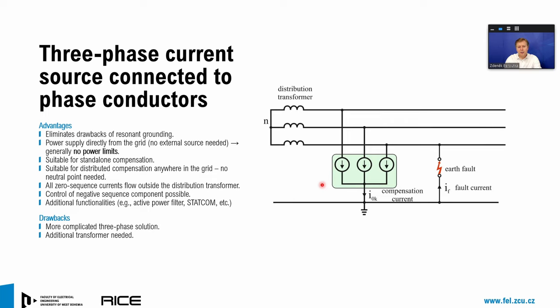This device is suitable for distributed compensation, which means that it can be installed anywhere in the grid. We do not need a neutral point for the installation of this device. All zero sequence currents flow outside the distribution transformer, and we can control the positive, negative, as well as zero sequence component. And in this configuration we can offer additional functionalities such as active power filtering, STATCOM functionality, and many other features. The penalty for this configuration is higher cost, and we need an additional transformer to be able to connect this device into the grid.